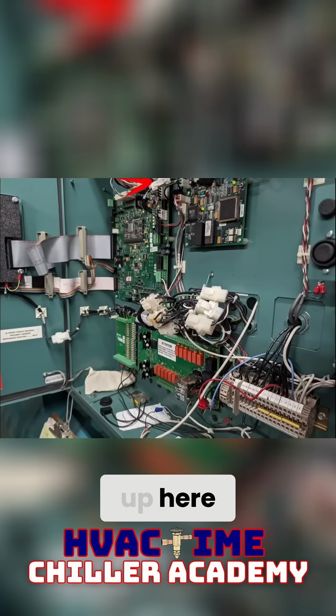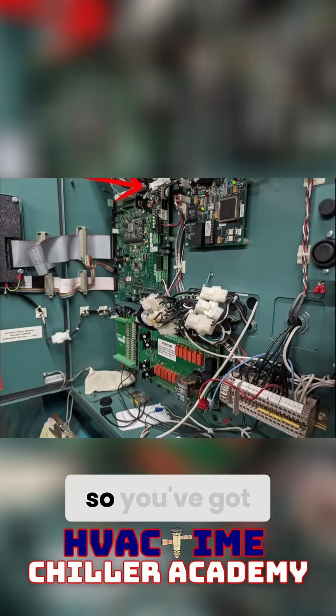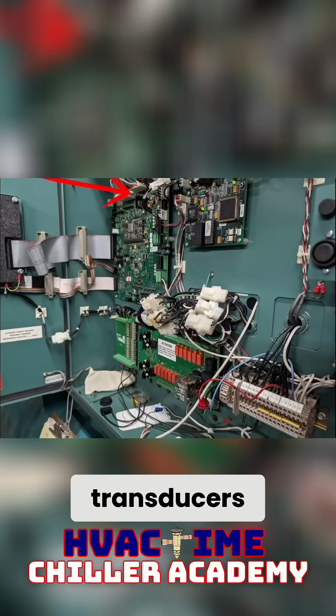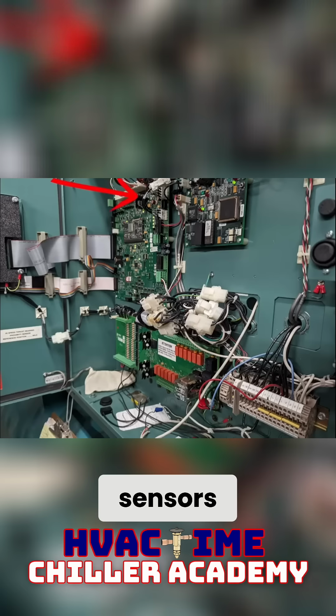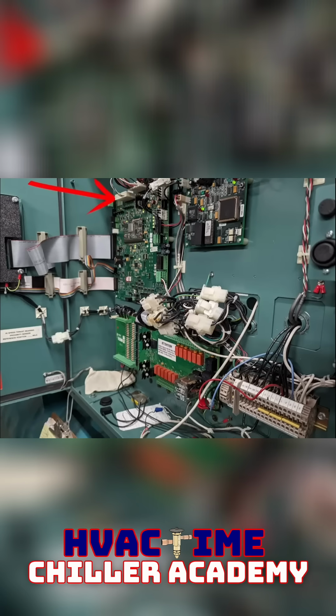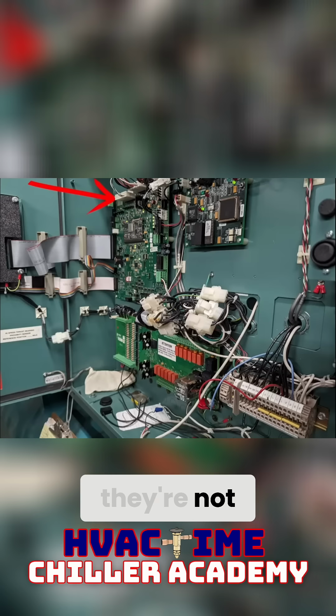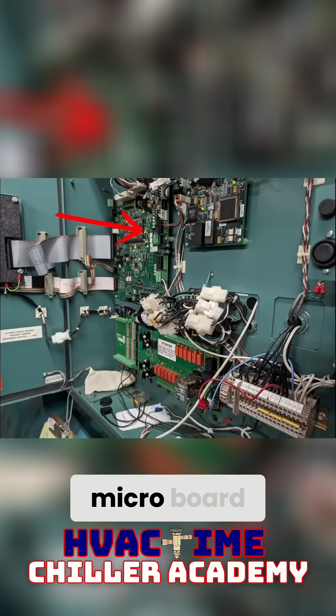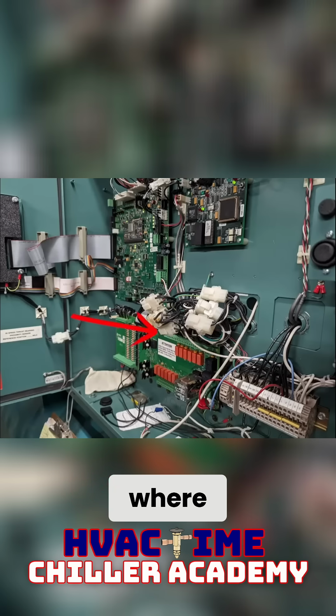But up here, these are your sensors. So you've got your temperature sensors, your transducers, your flow sensors. All of that is going through up here. But those are very light loads. They're not putting any major stress on the circuitry for the main micro board. And that is where this I/O board comes into play.